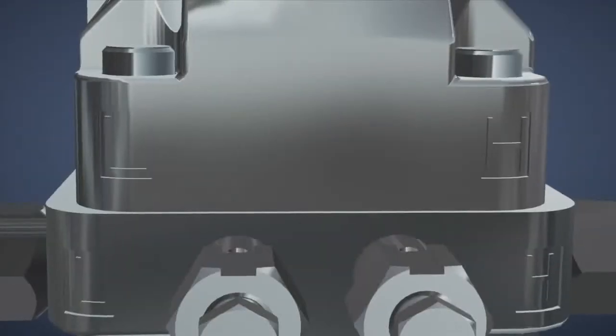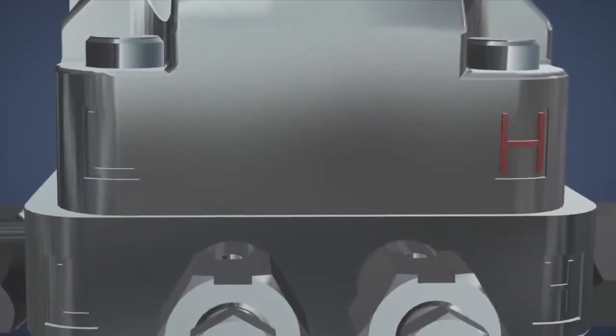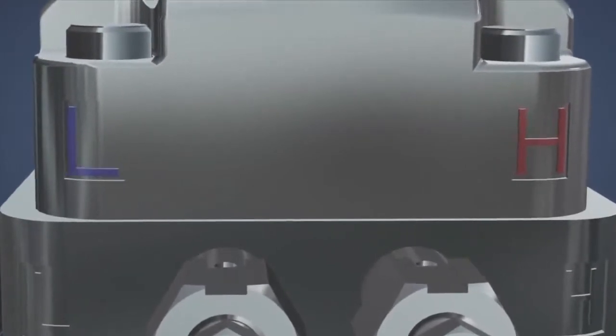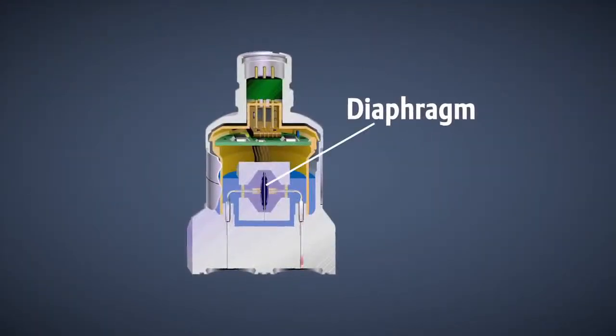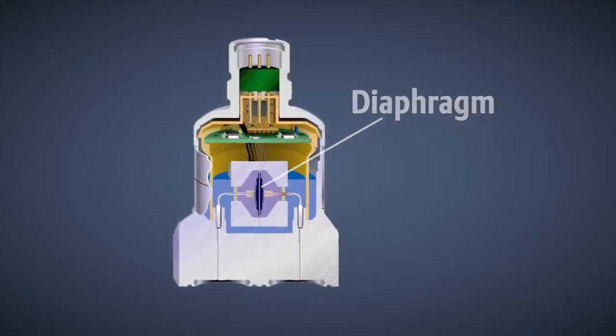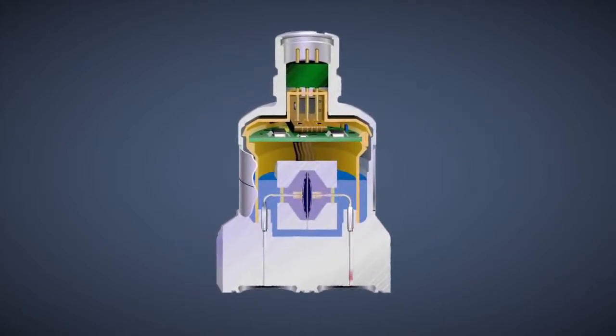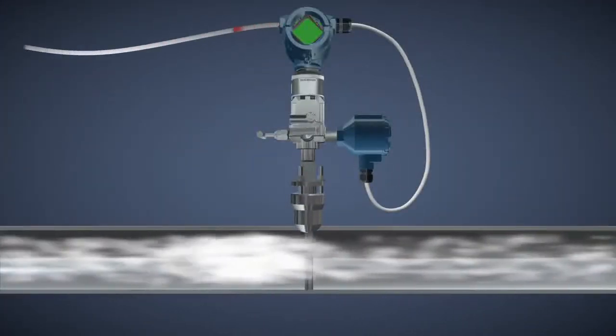On one side of the transmitter is the high-pressure side, on the other, the low-pressure side. The diaphragm deflects relative to the pressure change from one side to the other. It is very sensitive and can detect very small changes in pressure. The transmitter then relays the DP measurement to the control system.